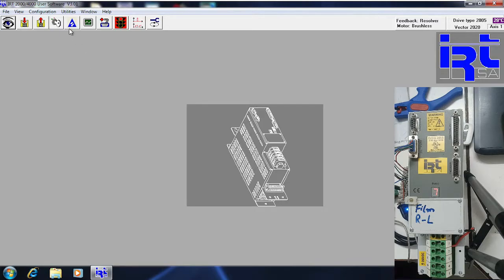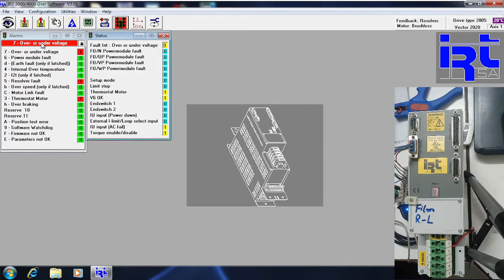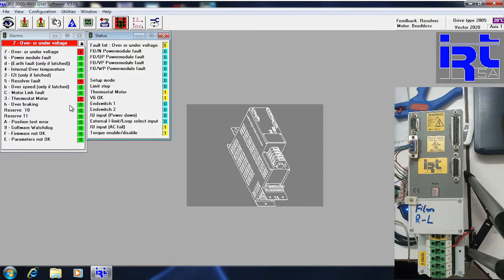This is the alarm status window. You can see all alarms appearing here — over/under voltage alarm, because I have connected a single-phase supply. It is also showing a thermostat motor alarm because I have not connected any motor to my drive. This is also the status taken from here.